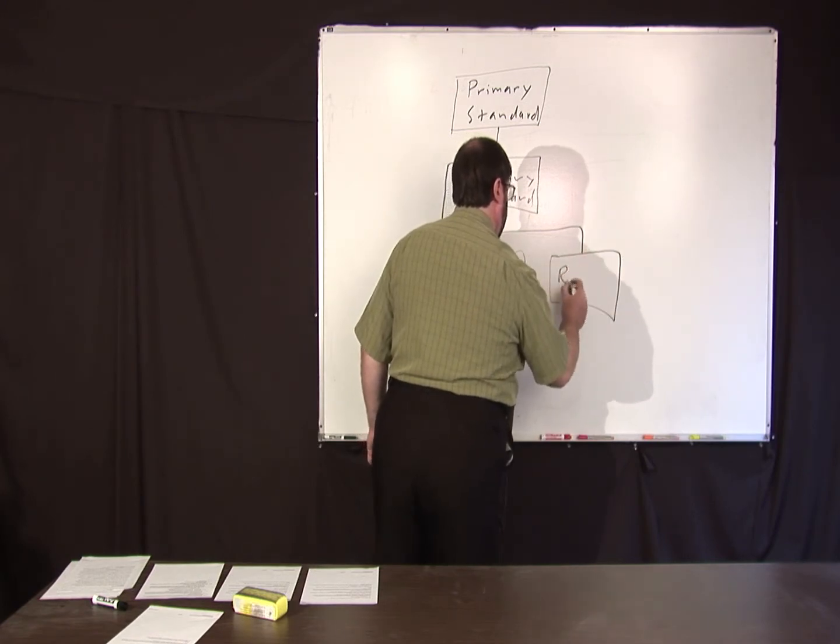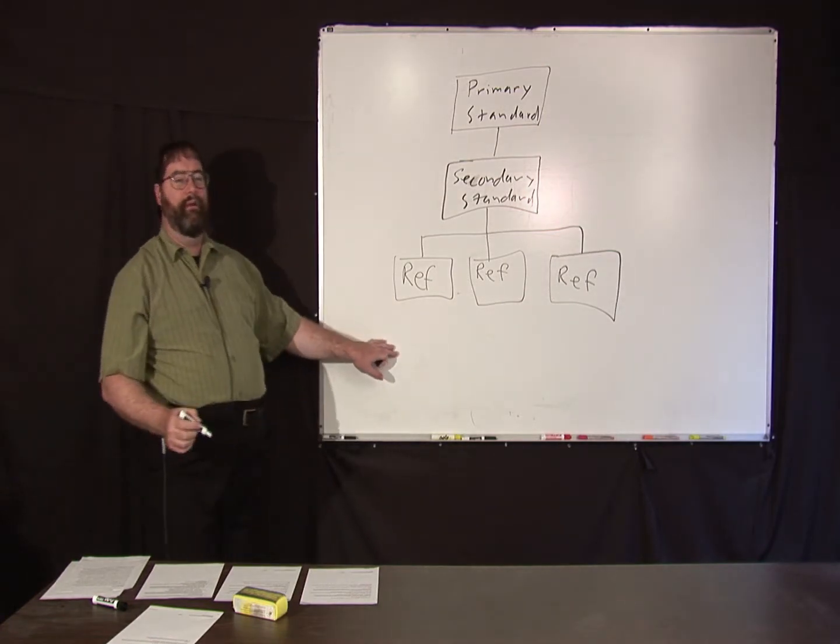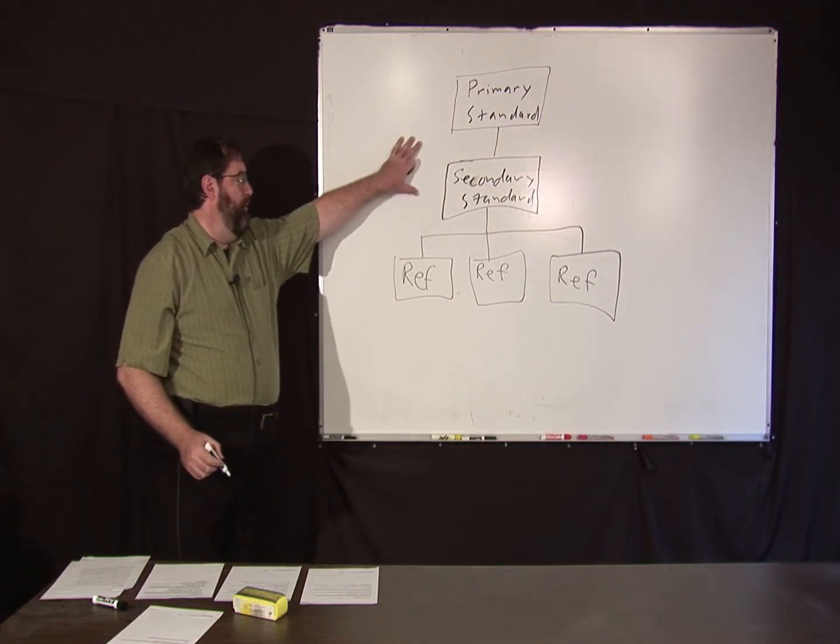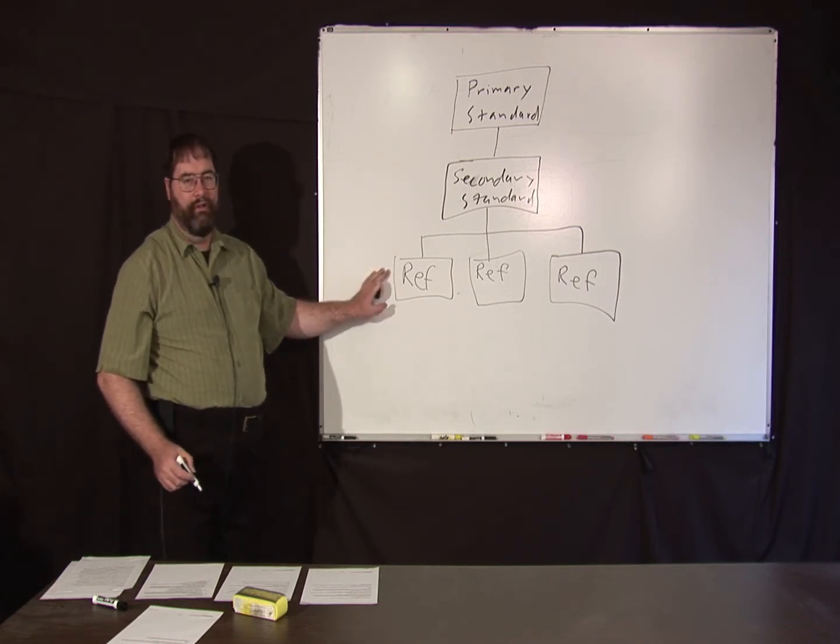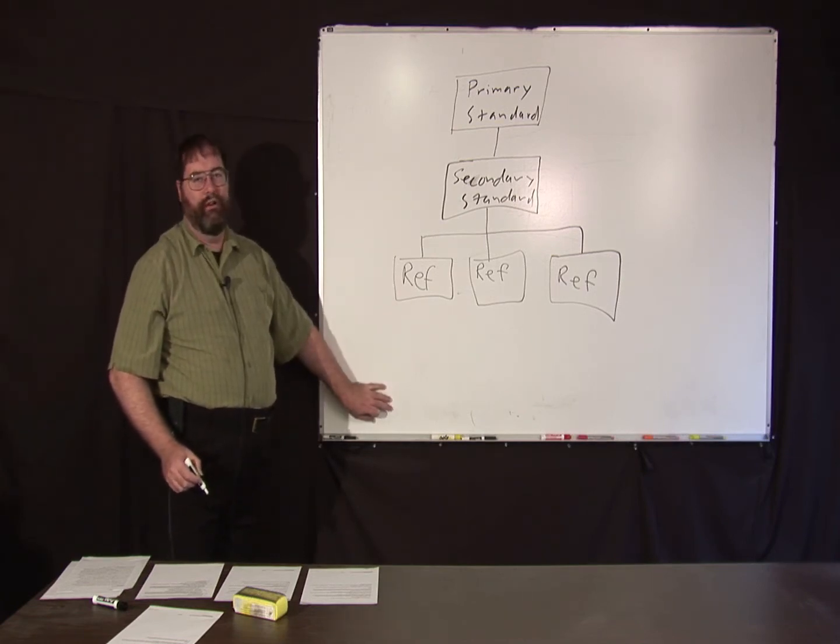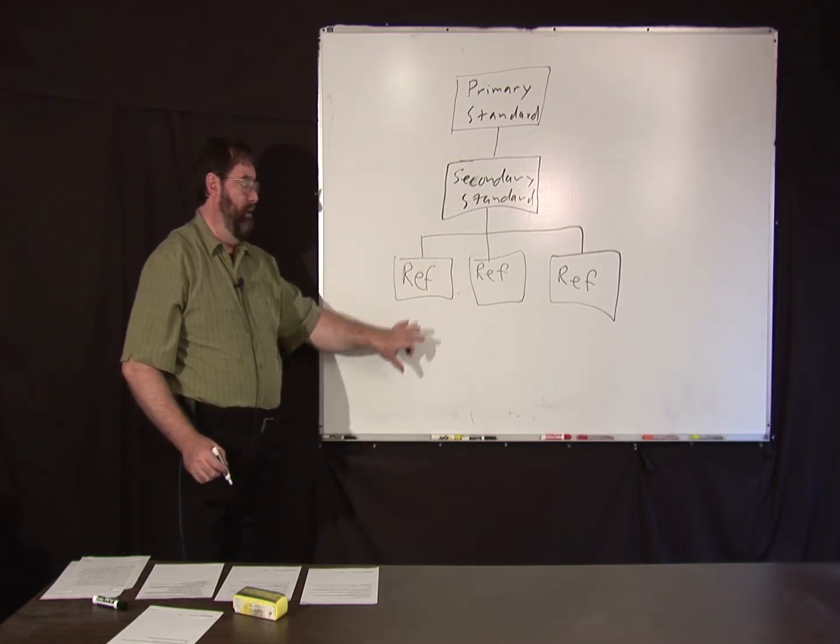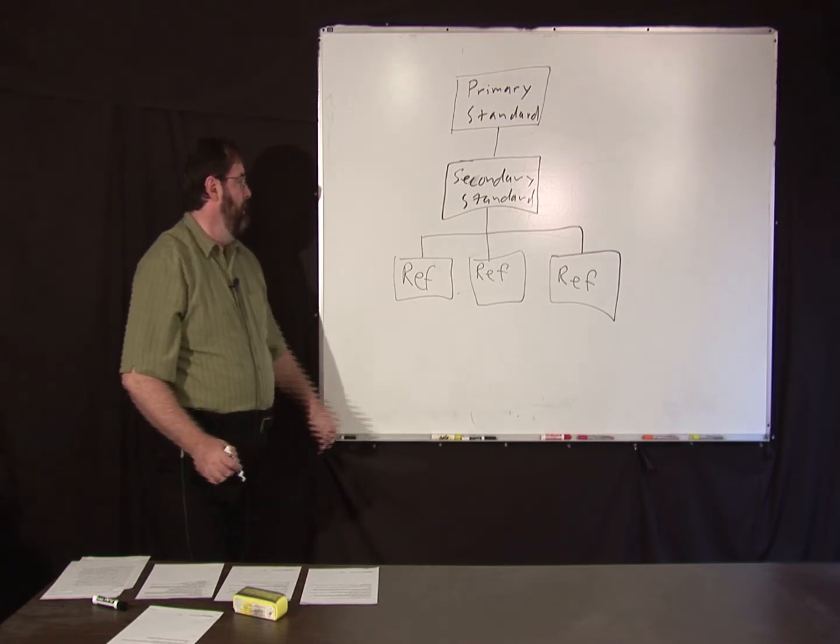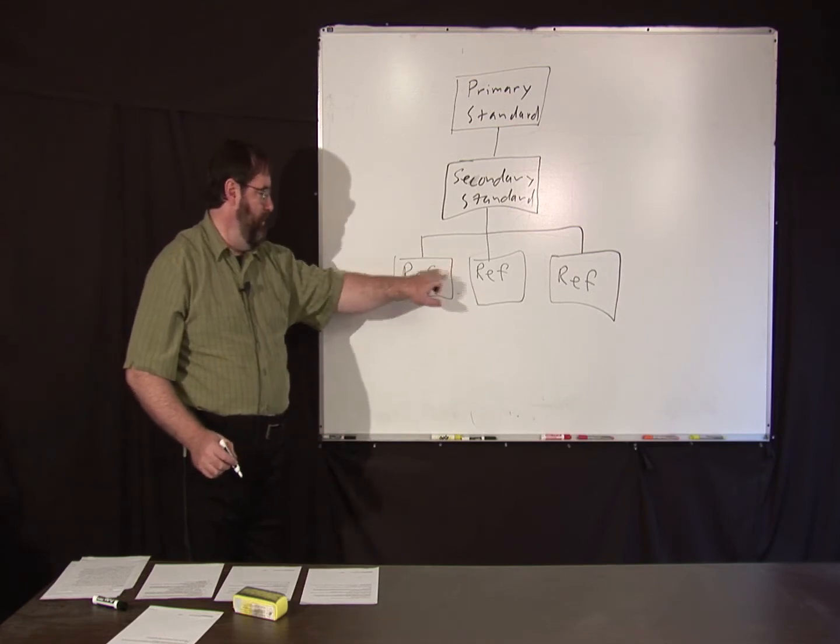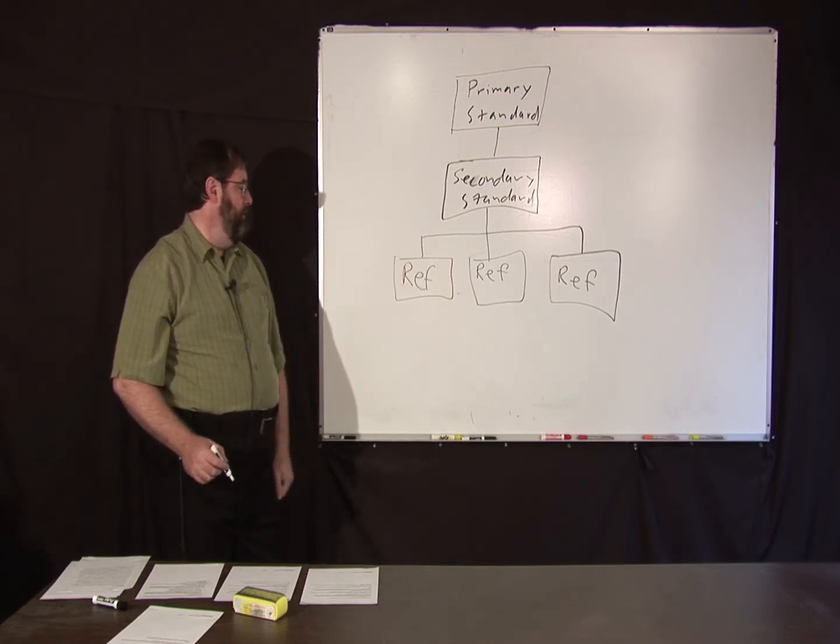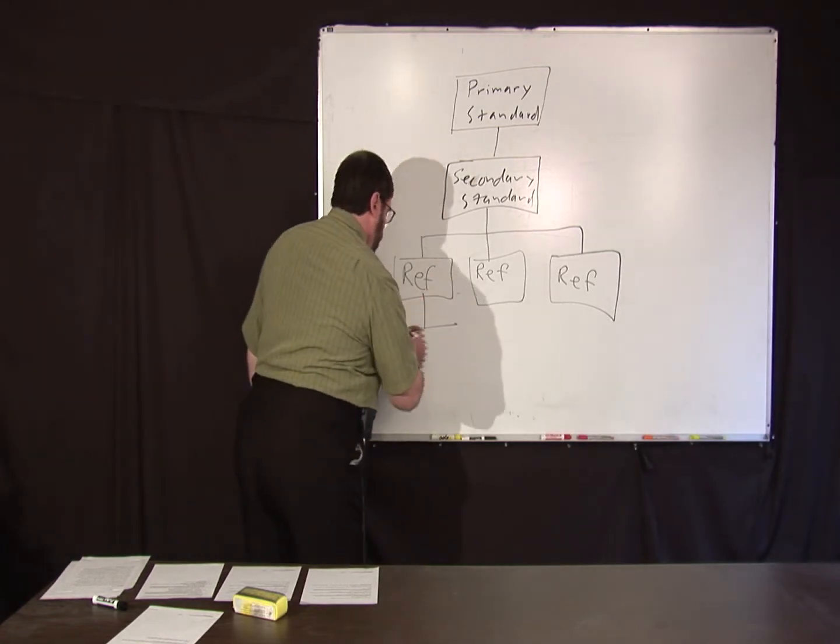And then there's usually another level below this. Or maybe this might also be used to calibrate other reference standards. For instance, this might be a primary lab at a company if it's big enough. And these could be secondary calibration labs. And you could have tertiary labs as well. So you might have a lab and then regional labs and then local labs. Or this could be a country's primary and these are companies and then they use these to calibrate other standards. And below this is something called a working standard.